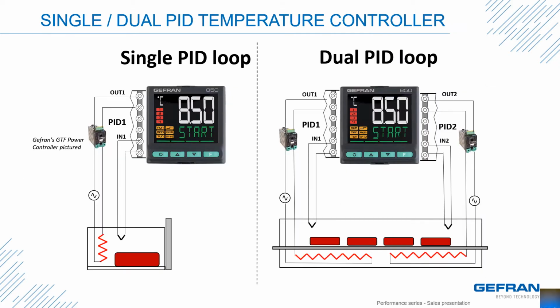I'm showing the Performance series as a closed loop controller. On the left, I'm showing the Performance series as a single loop PID controller. It has its connection to a thermocouple input. The output could be an analog output going to a GTF. Last week we heard Matt Fisher discuss the benefits of that power controller. What else could you do with this heating system? How about adding communications like Modbus RTU or Ethernet?